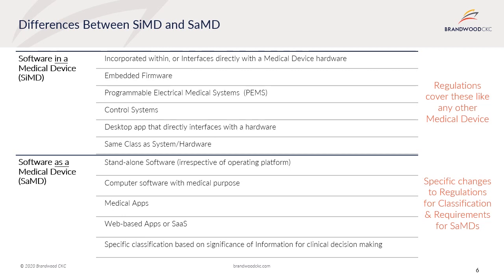Changes in regulations are being made, such as classification and requirements specific for software as a medical device. This is important as the current regulations do not include provisions for software and software as a medical device separate to physical medical devices. Where this poses particular challenges is that the classification rules that exist for medical devices currently only consider the possible harm caused by physical interaction of a medical device with a human. As software does not have this physical interaction, the risks relate more to analysis and calculation errors and inaccuracies in diagnosis and clinical treatment recommendations. Therefore a new specific classification framework is required.